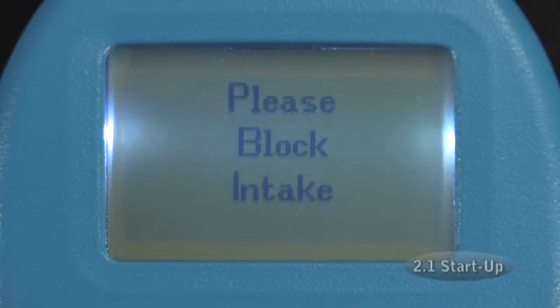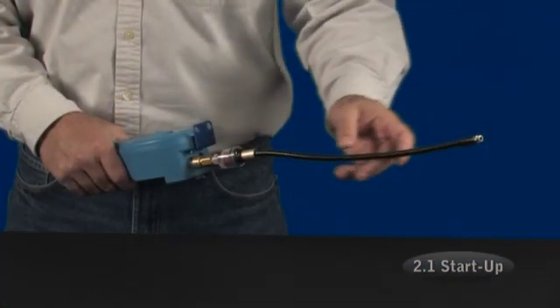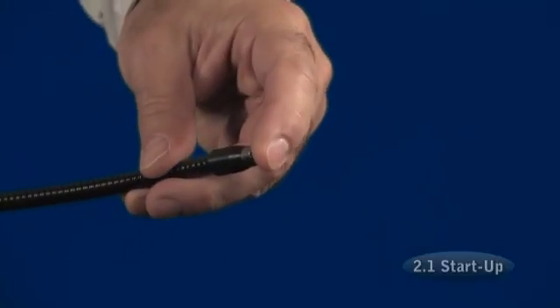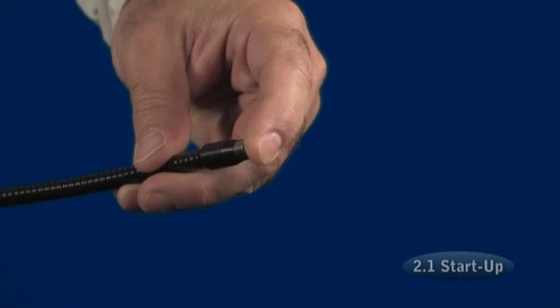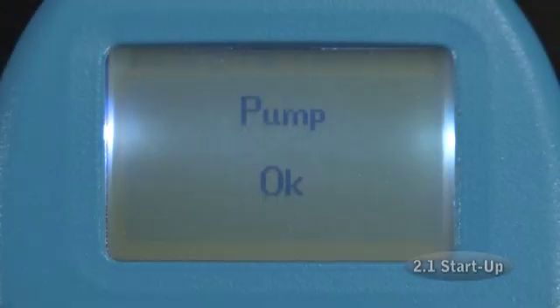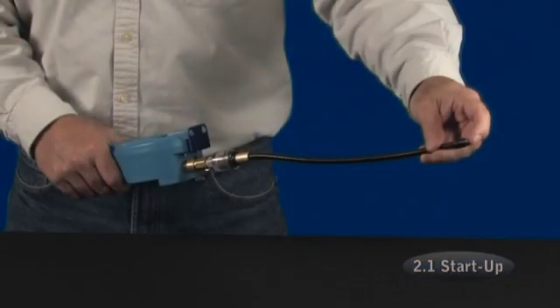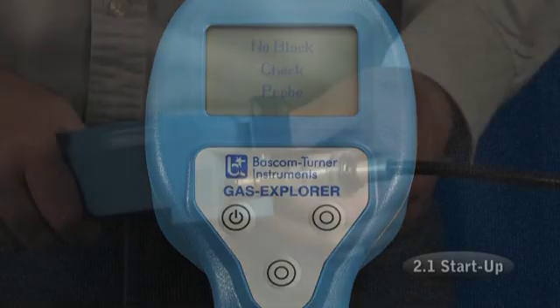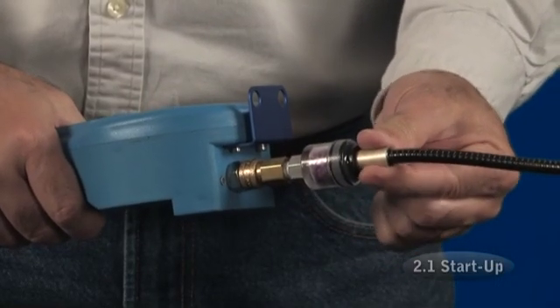The next screen will ask you to check the pump by blocking the intake. Completely block the opened end of the probe with your finger so that the Explorer can test its pump. After a moment, it will tell you that the pump is okay. If the instrument does not detect a block within 40 seconds, it will say, "No block, check probe." Make sure the probe connections are tight.